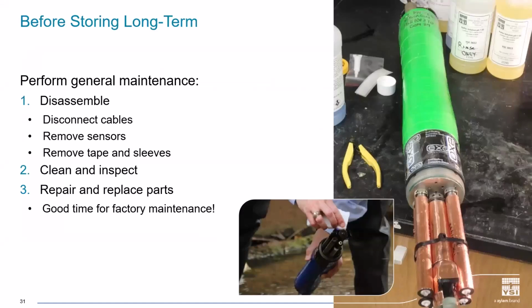You can see in this picture, the EXO has a green tape on it, and that was to prevent growth on the sonde, or to help easily remove growth on the sonde, and then copper tape on the sensors for anti-fouling. And you can take all that off. Once you take it off, you can make sure everything's clean and really inspect everything for damage. And then take the time to repair and replace parts. That way everything is ready to go for next time. And since you're going to store your equipment for a long period, this might also be a good time to send your equipment in for factory maintenance, since you'll be having instrument downtime anyway.